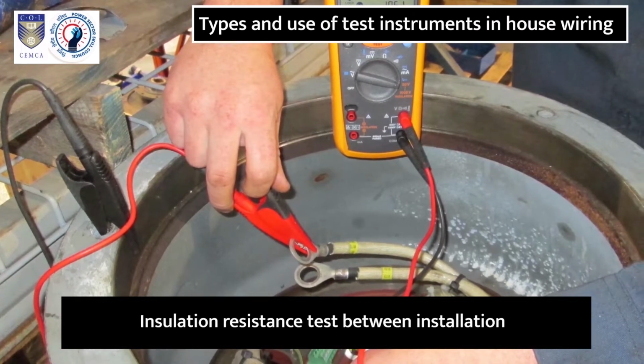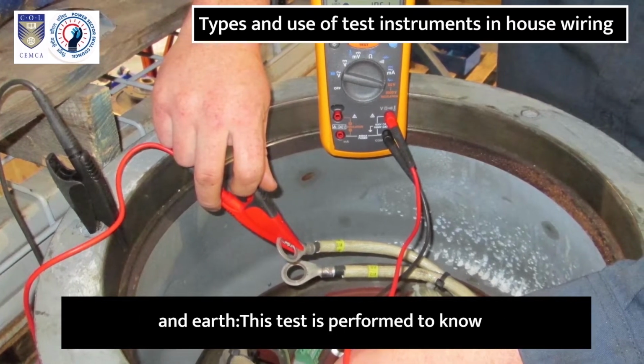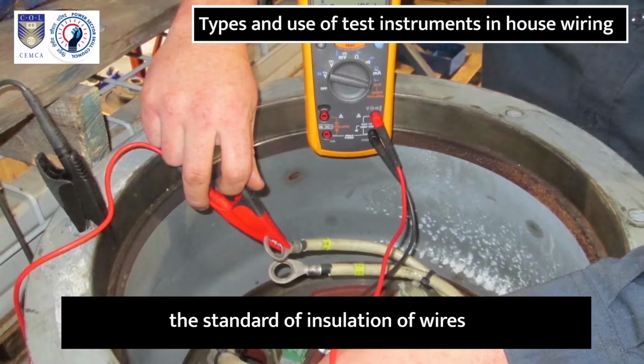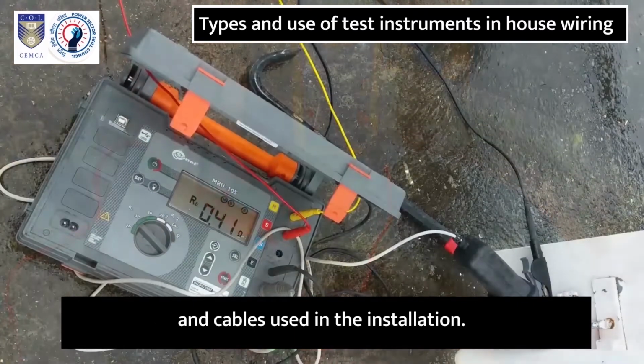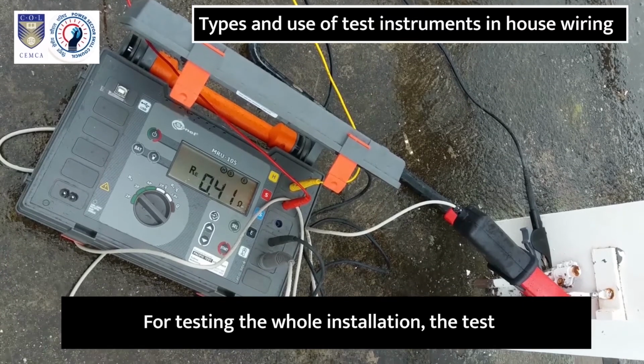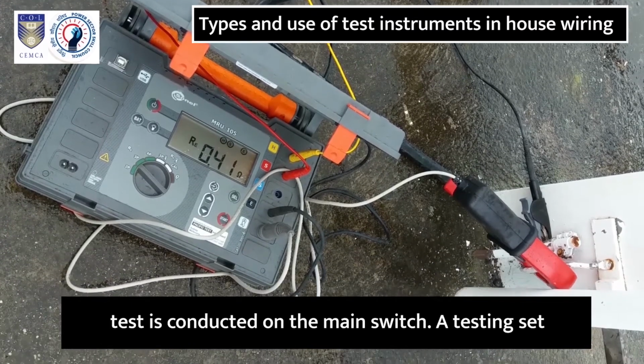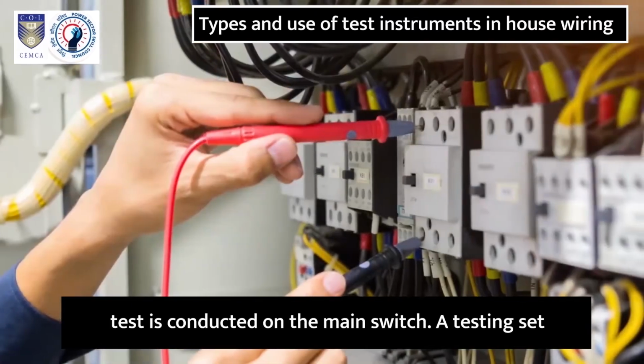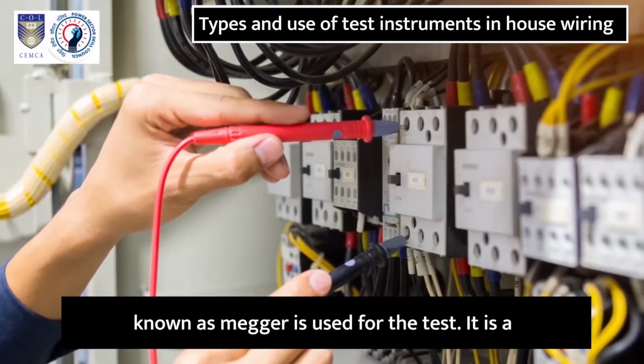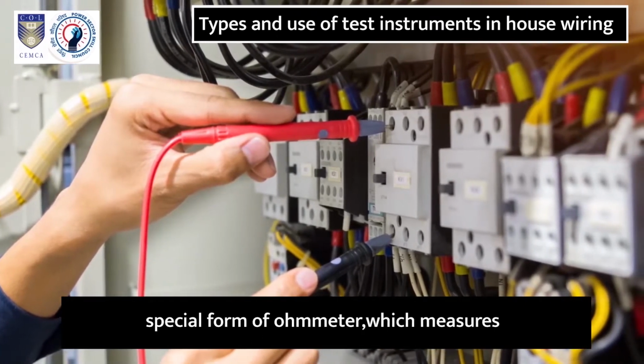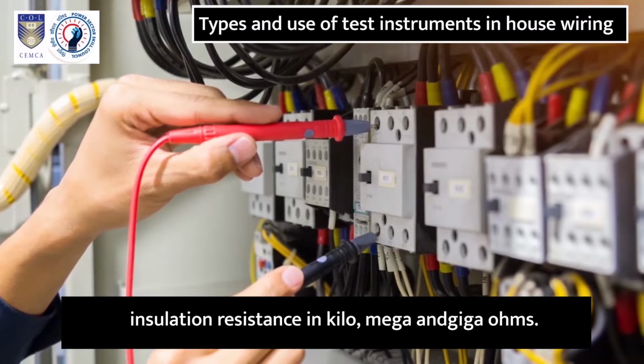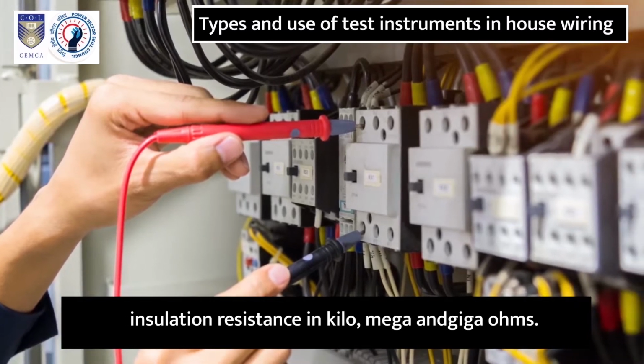Insulation resistance test between installation and earth. This test is performed to know the standard of insulation of wires and cables used in the installation. For testing the whole installation, the test is conducted on the main switch. A testing set known as megger is used for the test. It is a special form of ohm meter which measures insulation resistance in kilo, mega and giga ohms.